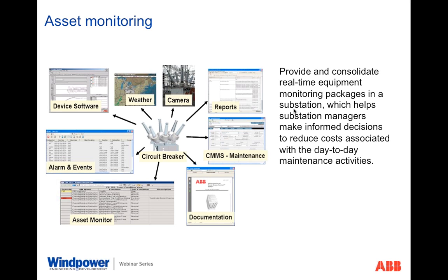So in the case of a maintenance manager, we do a similar concept for many areas of a circuit breaker, such as repairing or topping off SF6 gas, fixing a heater coil before a temperature becomes an issue, even determining the mechanical integrity of the mechanism upon each operation. These are just some of the areas of improved efficiency that users can realize with condition-based maintenance practices. Here, in this particular picture, we are showing how an asset management system can consolidate information into a single user interface, regardless of the many different types of information that may reside in multiple data sources.